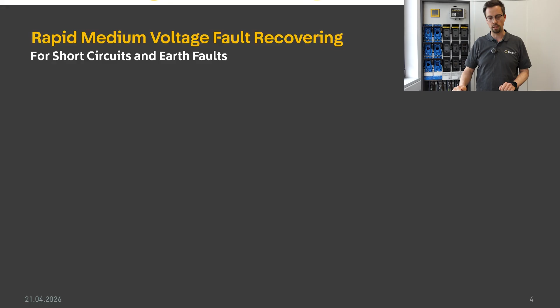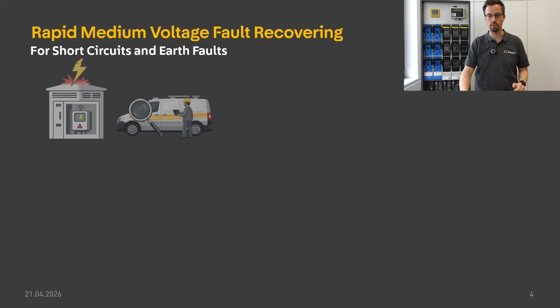So let's first try to understand where some network operators are today. A medium voltage fault can happen out there - it could be a tree falling on a line, a digger digging through a cable, or something else. These things happen. At the moment, a lot of network operators will have fault passage indicators, which will indicate in the actual substation where the fault has occurred. So there are devices out there that can detect this, but generally these are offline.